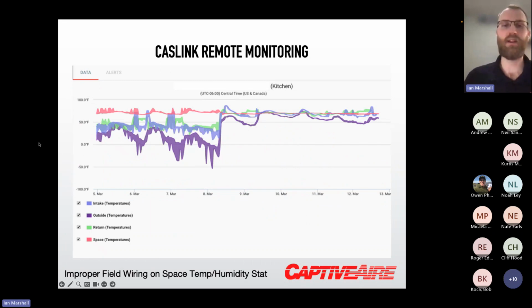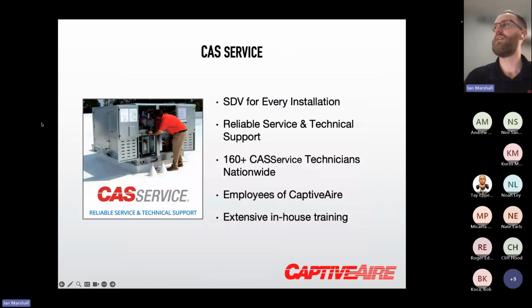The last one here was we were getting readings that weren't making a ton of sense, and we were seeing outdoor air temps showing like -50, which we knew was not accurate. When we get those kind of readings, we know sometimes that the thermostat was miswired, and it turns out they just miswired 2 of the wires on the thermostat. So they got those resolved, and all the temperatures came back right into range as expected.